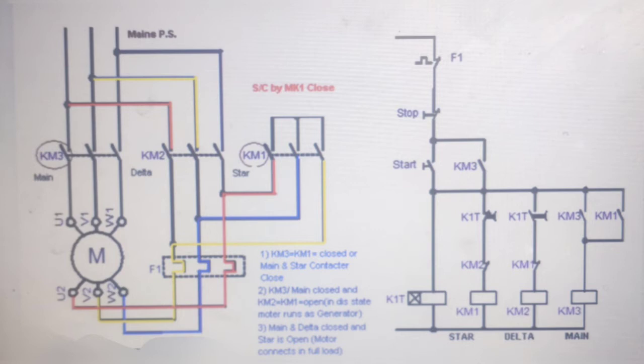The third conductor is the star conductor and that only carries the star current. The current in star is one third of the current in delta, so this conductor can be AC3 rated at one third of the motor rating.